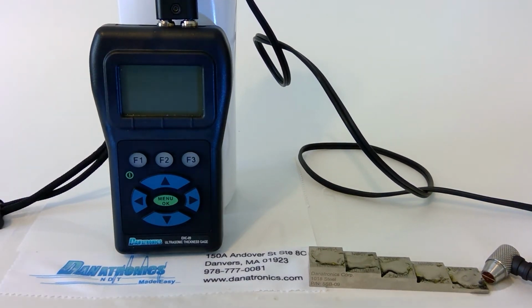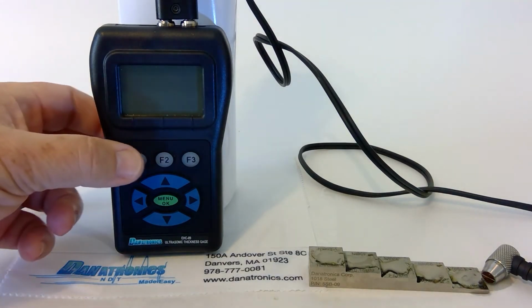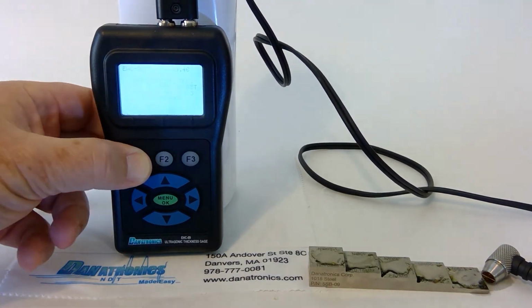The Danatronics EHC-09 has two modes of calibration: the manual two-step and the new auto cal. Let's go over the procedures for each. First, we turn on the gauge by pressing the F1 button.